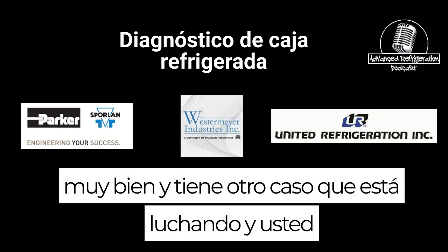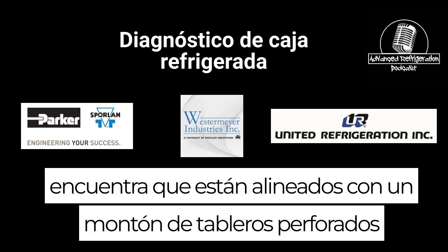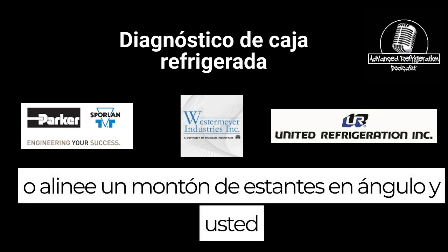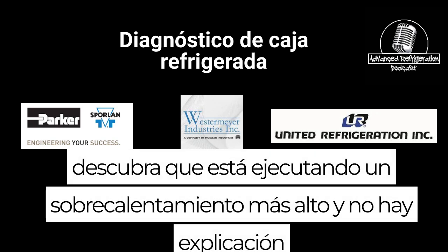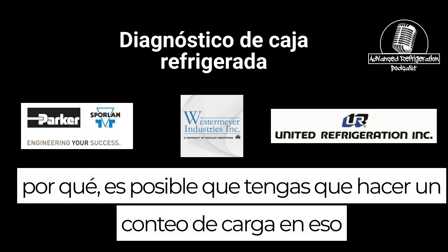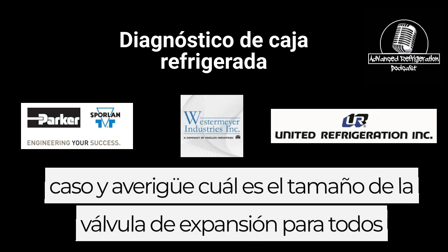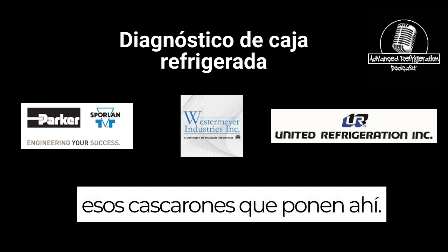So be mindful if you have two cases that are running just fine and you have another case that's struggling, and you find that it lines up with a whole bunch of pegboard or a whole bunch of angled shelves, and you find that it's running a higher superheat and there's no explanation why. You might have to do a load count on that case and figure out, is the expansion valve sized for all those angle shelves that they put in there, or is it not?